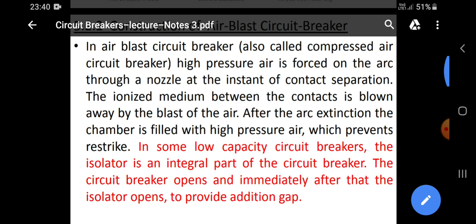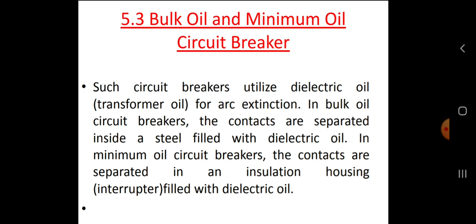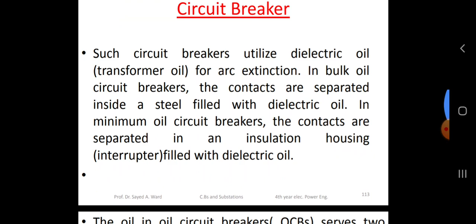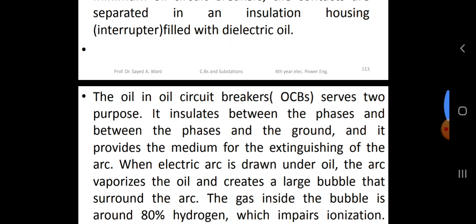So the next type of circuit breaker is the bulk oil and minimum oil circuit breaker. Such circuit breakers utilize dielectric oil for arc extinction. In bulk oil circuit breakers, the contacts are separated inside a steel tank filled with dielectric oil. In minimum oil circuit breakers, the contacts are separated in an insulating housing filled with dielectric oil. The oil in an oil circuit breaker serves two purposes. It insulates between the phase and the ground, and it provides a medium for the extinction of the arc.